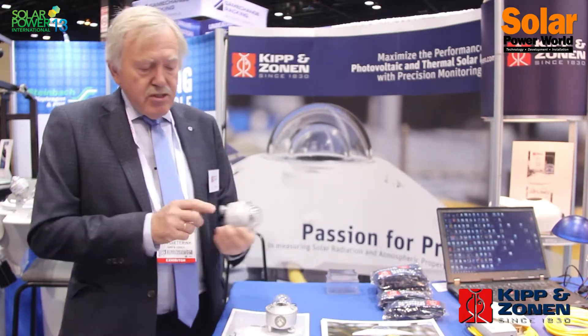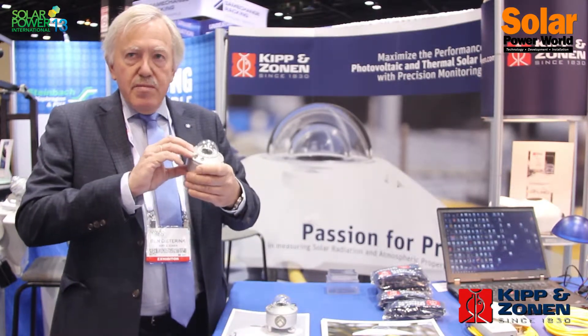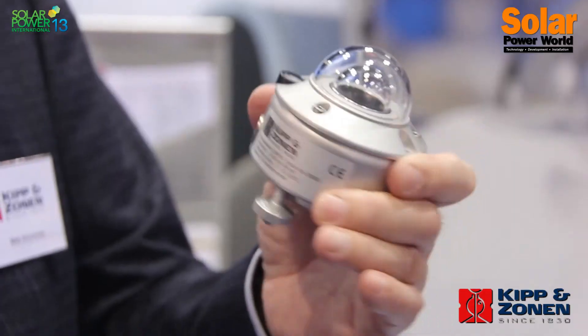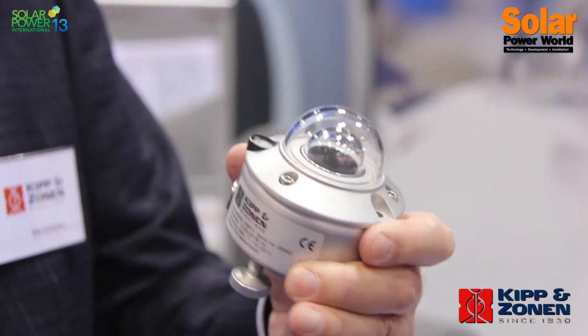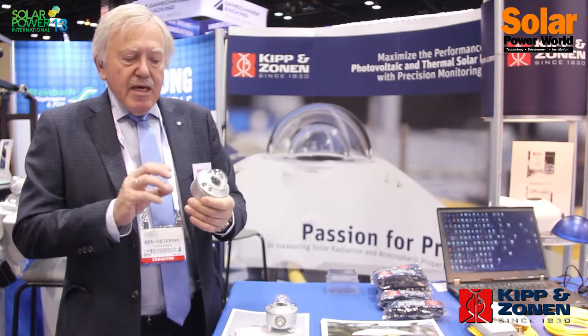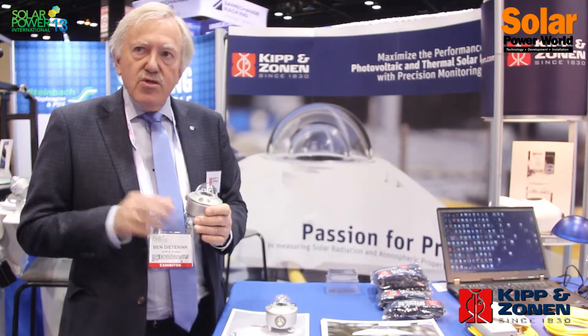What we have done is take out the replaceable cartridge, make the sensor in a better way with better bonding, and put a permanent cartridge inside so we can guarantee that the internal area of the sensor is always stable in dry air.